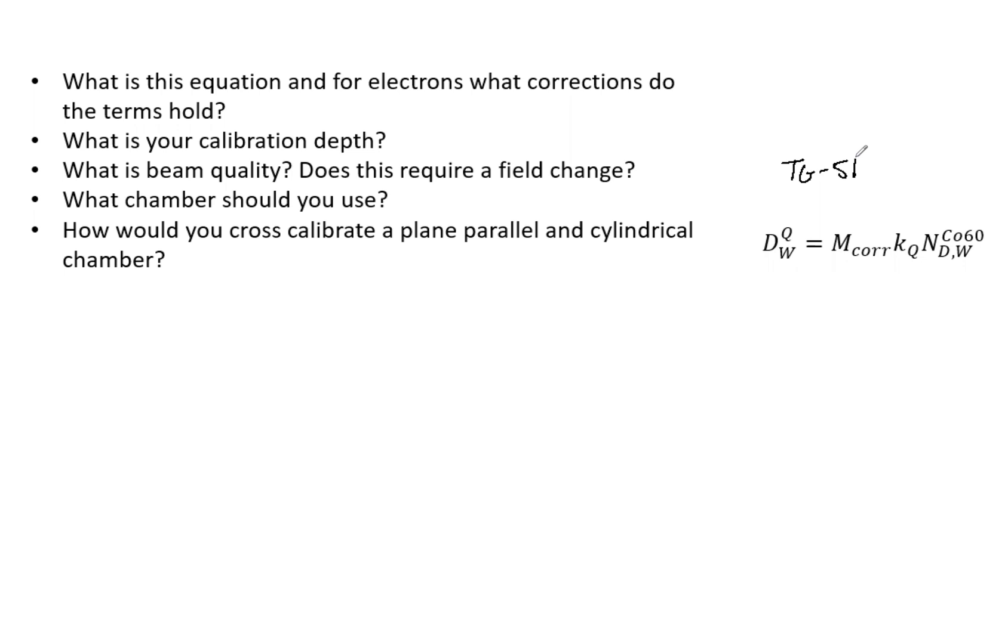And we have correction factors to account for this. Let's break this down. The M corrected is the raw reading, typically in nanocoulombs. You then have your P-elect, the electrometer correction factor. You have your P-ion, the ion recombination. You have P-pol, the polarity correction. P-TP, the temperature and pressure correction.